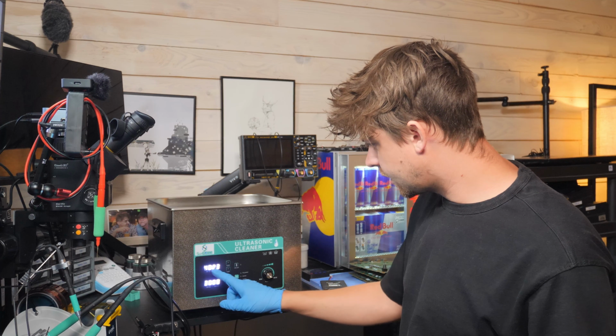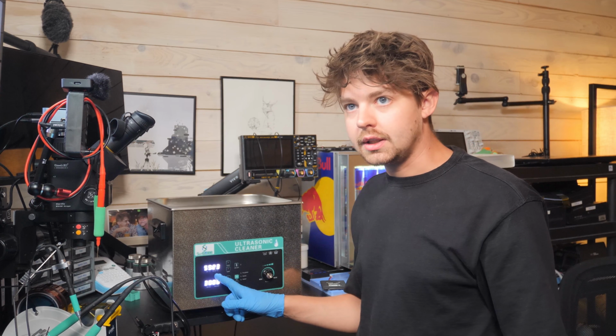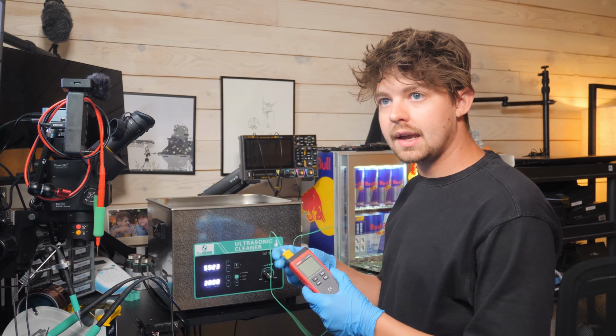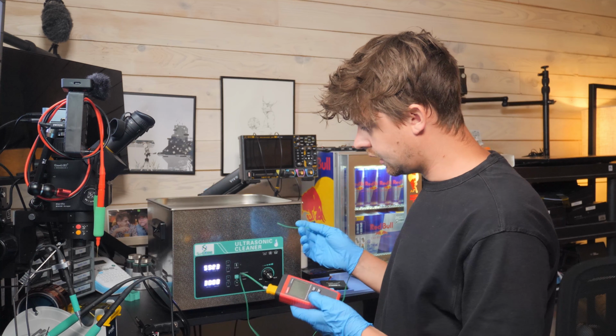We've got a nice display. So you can see the set temperature is at 40. I guess you guys can't see that very well, but I'm going to set this up to 55 degrees Celsius. It's currently measuring the liquid at 23 degrees Celsius. So I'm going to time how long it takes for it to get up to temp. And I'll also check with a K-type thermocouple to see how hot the liquid actually is.